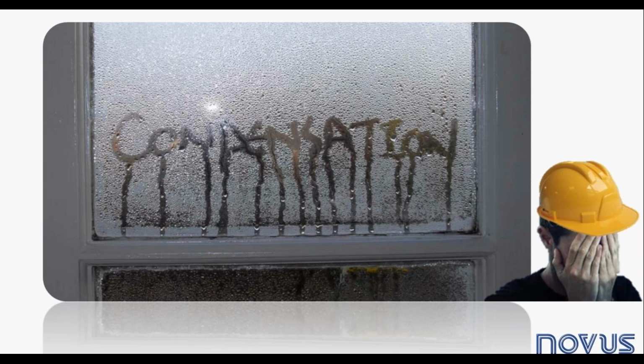Many of those processes, due to the nature of the product, require humidity control in very narrow tolerance, sometimes on the threshold border of temperature or humidity, and the limit of condensation or frost. The strict control of water vapor and air mixing ratio is a key factor for improved air quality in those processes.